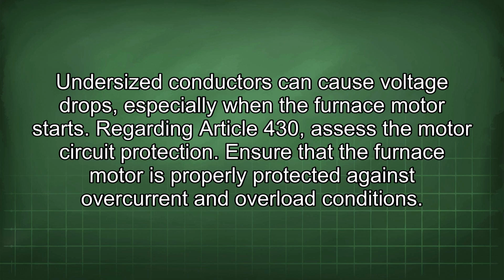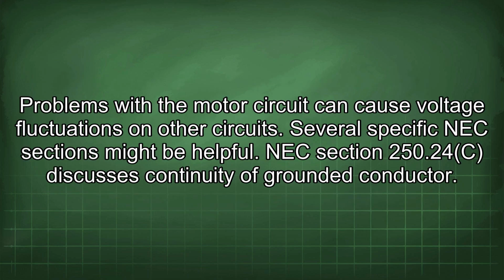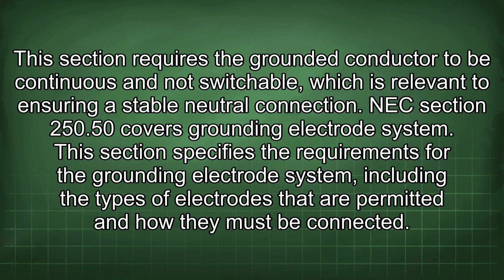Regarding Article 430, assess the motor circuit protection. Ensure that the furnace motor is properly protected against overcurrent and overload conditions. Problems with the motor circuit can cause voltage fluctuations on other circuits. Several specific NEC sections might be helpful. NEC Section 250.24(C) discusses continuity of grounded conductor. This section requires the grounded conductor to be continuous and not switchable, which is relevant to ensuring a stable neutral connection. NEC Section 250.50 covers grounding electrode system.